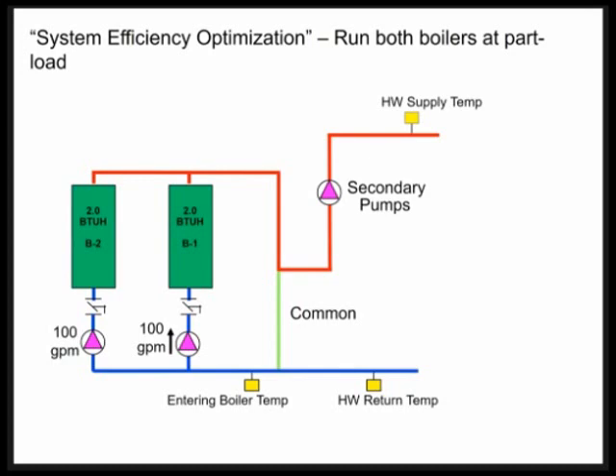You've got to pay attention to the return water temperature in the primary, especially when the primary flow is greater than secondary. With the constant flow primary, variable flow secondary, system efficiency staging might not be the most efficient. Let's look at that.